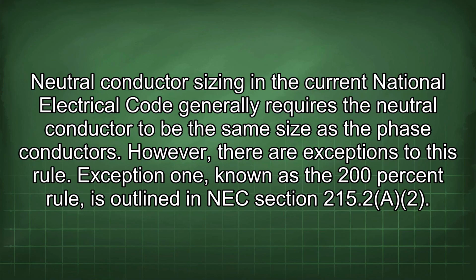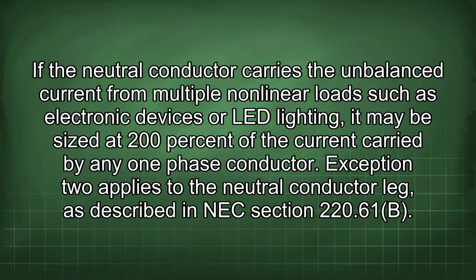Neutral conductor sizing in the current National Electrical Code generally requires the neutral conductor to be the same size as the phase conductors. However, there are exceptions to this rule. Exception 1, known as the 200% rule, is outlined in NEC section 215.2(A)(1). If the neutral conductor carries the unbalanced current from multiple nonlinear loads such as electronic devices or LED lighting, it may be sized at 200% of the current carried by any one phase conductor.